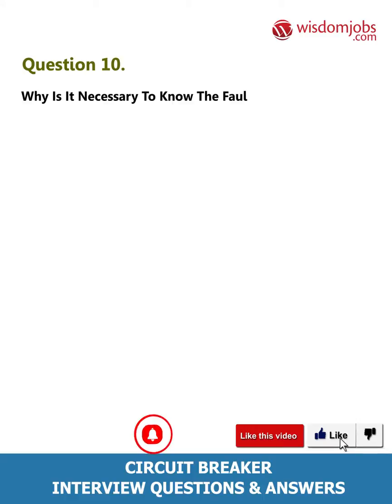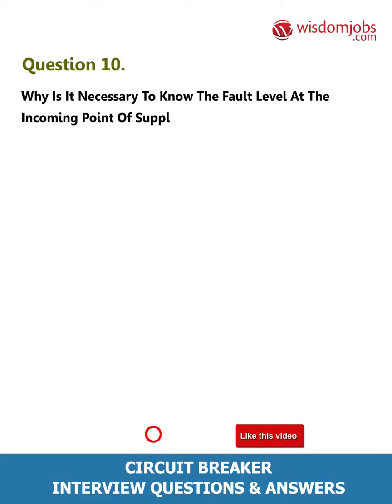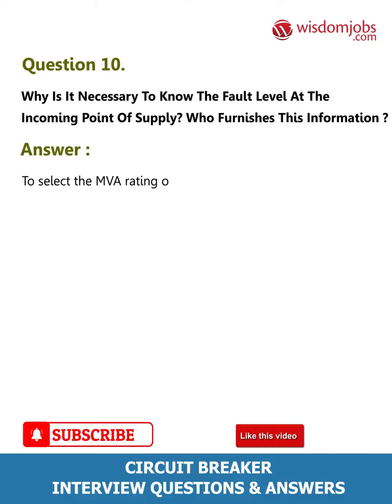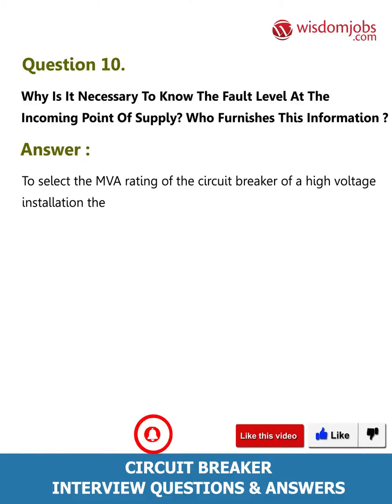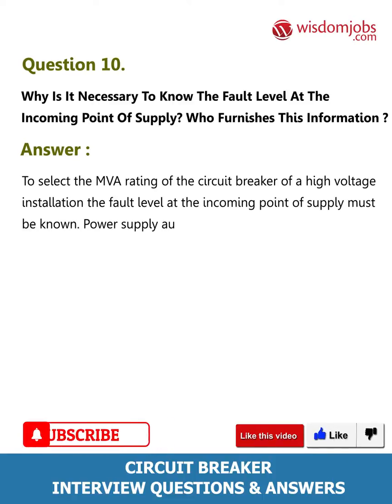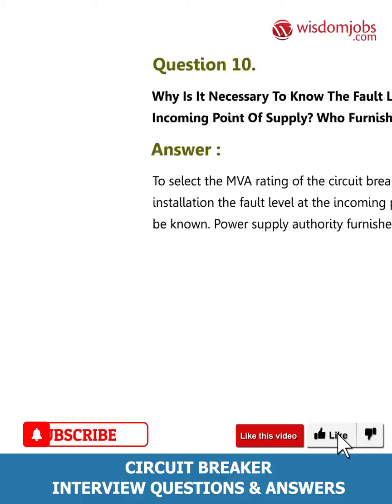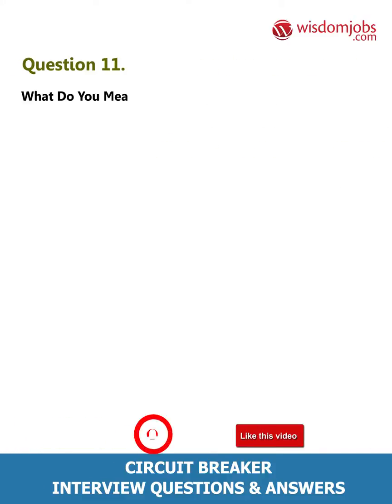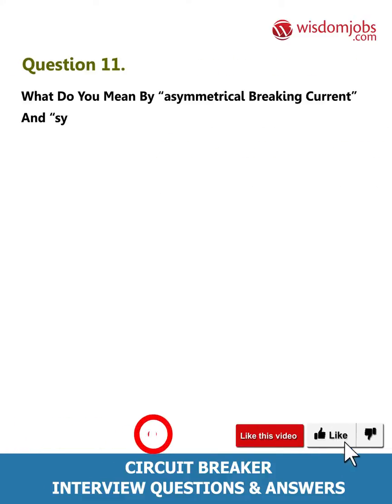Question 10: Why is it necessary to know the fault level at the incoming point of supply, and who furnishes this information? Answer: To select the MVA rating of the circuit breaker of a high voltage installation, the fault level at the incoming point of supply must be known. The power supply authority furnishes the fault level. Question 11: What do you mean by asymmetrical breaking current and symmetrical breaking current?